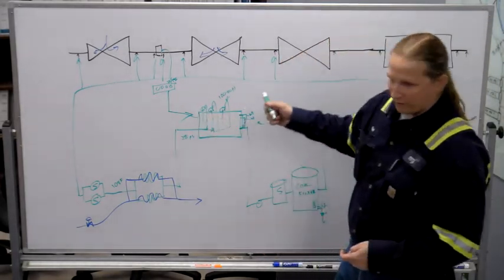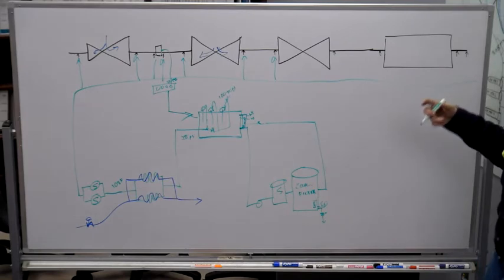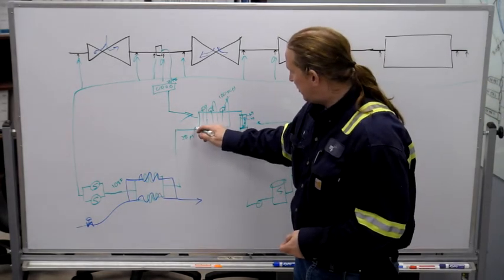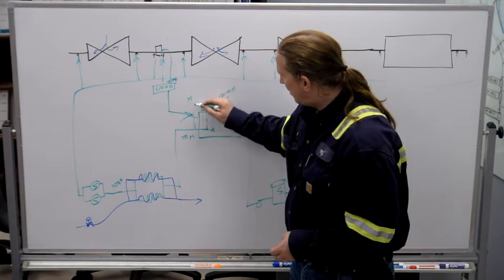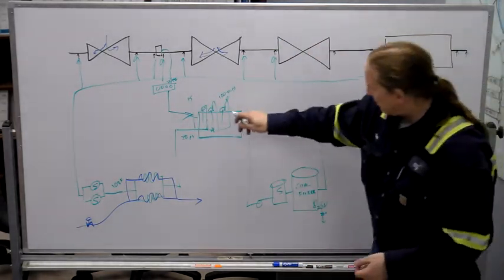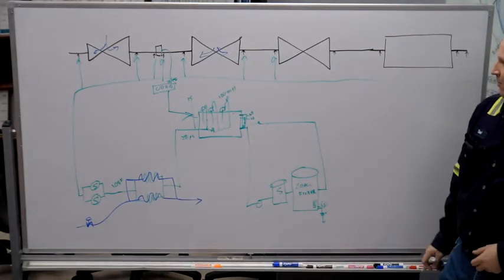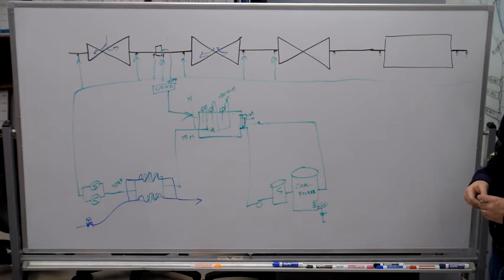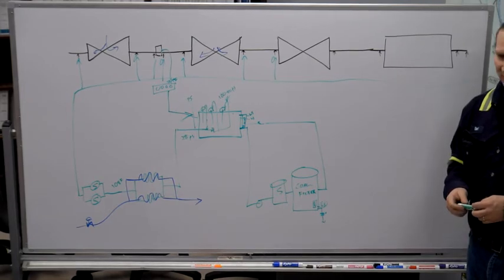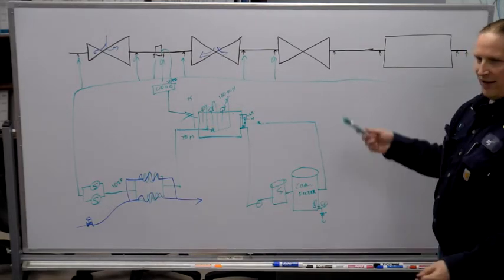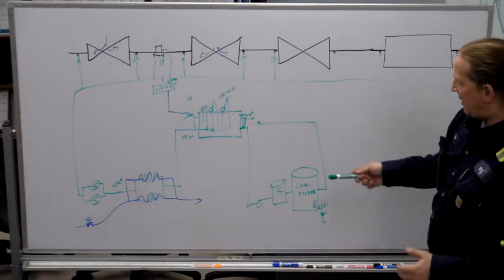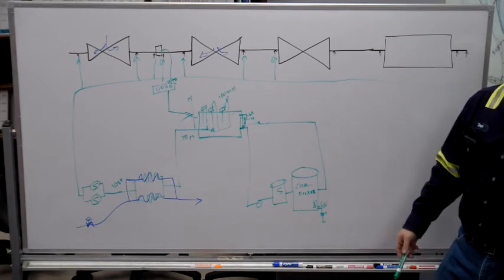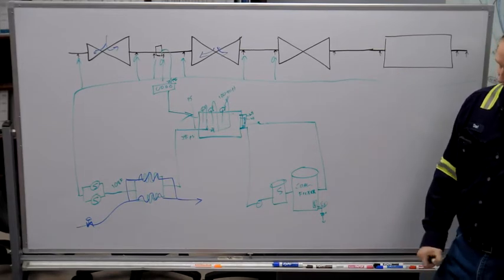Okay, so you have an emergency pump that is powered from the DC system. It's coming straight off the battery, so it is more reliable power. And then there's pressure switches. And there's a weekly test where you leave the pressure off the pressure switch and you watch the pump start, and you swap the AC pump, and then you watch the DC pump start. Does it say in there to run it for five minutes? No, but Wayne did the last time. So it used to say you run it for five minutes, and then somebody dug in the manual and said, why the hell are we doing this? There's no reason to do this. And I, being a Navy electrician that's worked around DC pumps before, says, well, there's a 30 minute requirement to have a monthly 30 minute run to keep the commutator in shape. Does commutator mean anything?